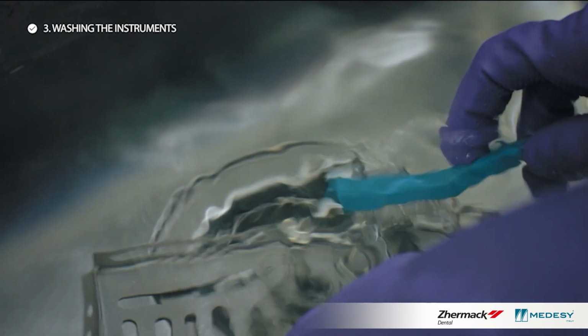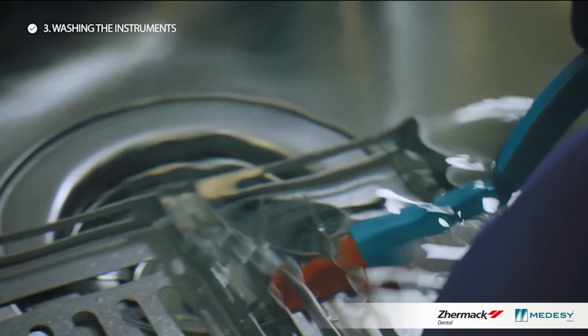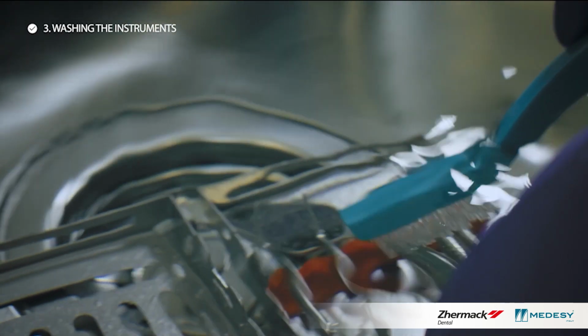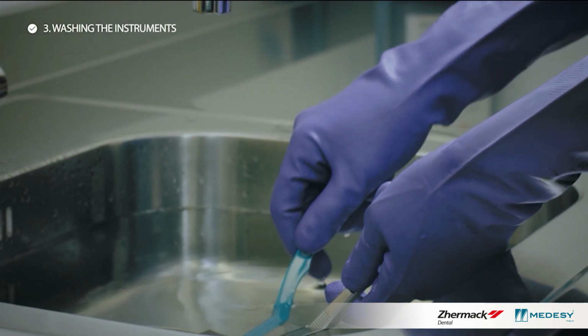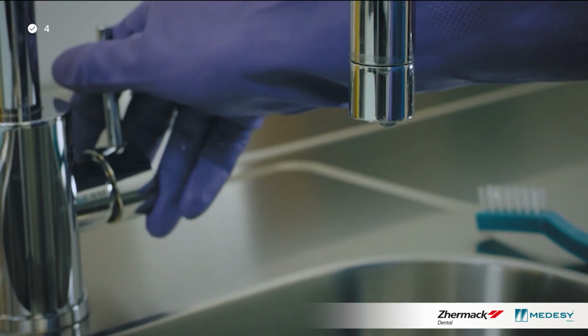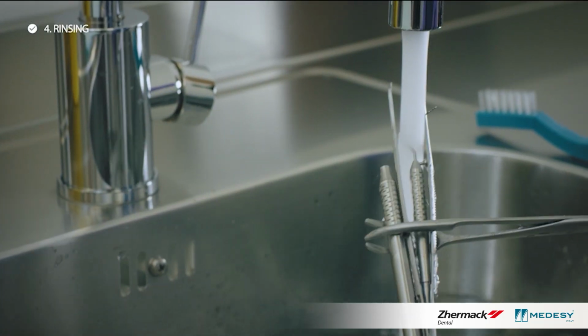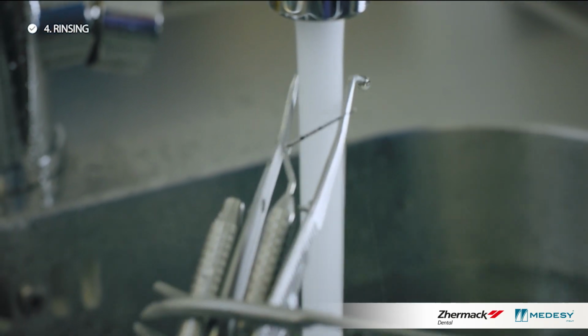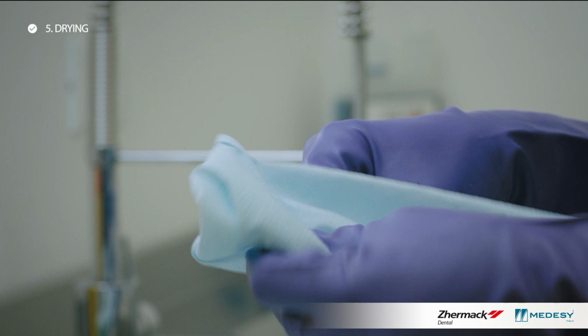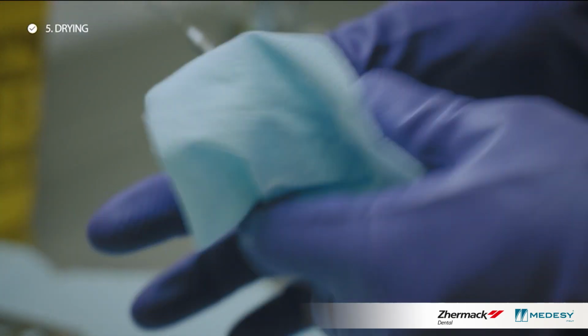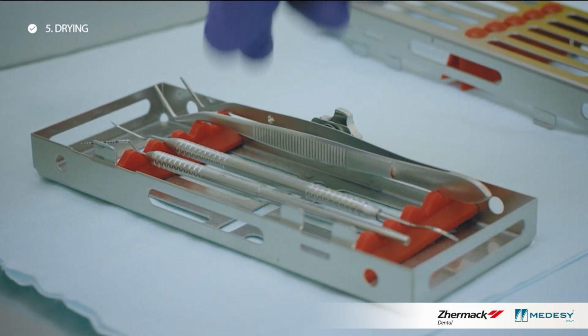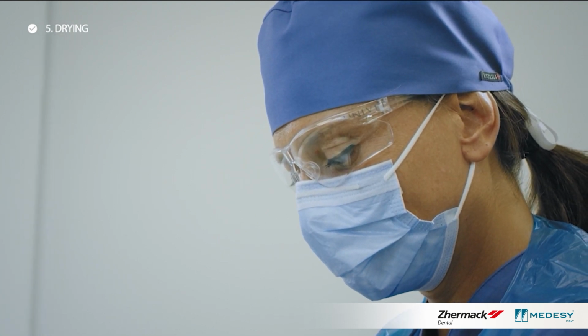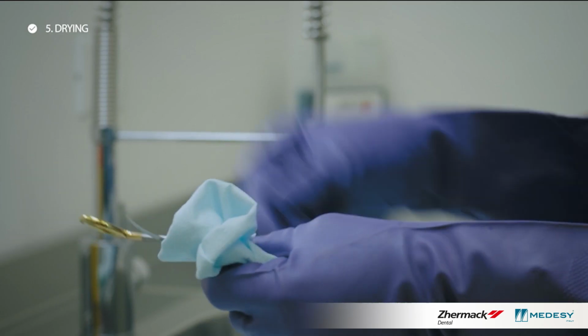Manual cleaning involves cleaning the disassembled instruments using a non-metallic brush while they are immersed in a cleaning and disinfectant solution. Remember to wear specific gloves while you do this. After the disinfection and washing, the instruments must be rinsed thoroughly before drying. Moisture could compromise the outcome of sterilization and lead to the formation of marks on the surface of the instrument. Dry the instruments manually, preferably with a disposable cloth which does not leave fibers, or with compressed air.